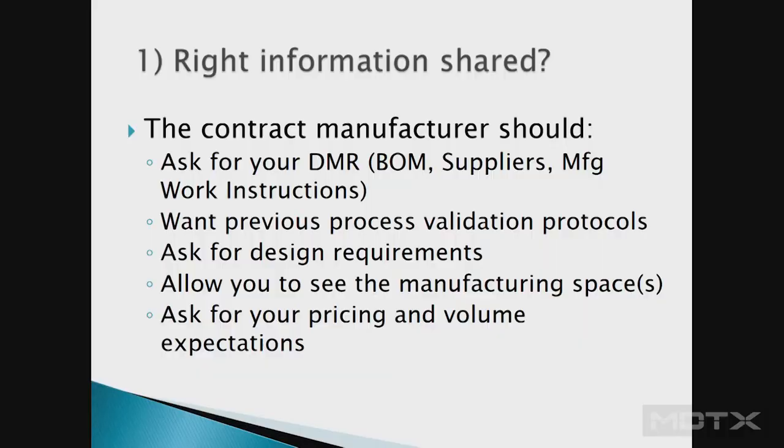The right information to be shared: the contract manufacturer should be asking you for your device master record. You have to bid this project out and quote it. They're going to need to know your bill of materials, who your suppliers are, and whether you have manufacturing work instructions. If you're moving it from in-house, they'll want everything in your device master record. If you're a brand new medical device company and haven't built it yet, that has to be the expectation of the manufacturing process.